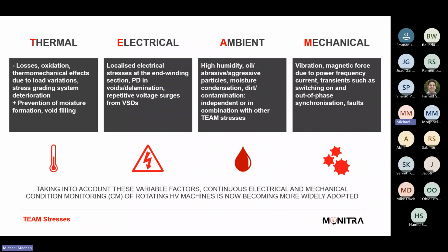So PD is a symptom and not a cause of a failure. Obviously when we look at PD, we're not looking at the potential cause. PD is purely a symptom of a potential failure mode. So an end winding discharge, a contaminated winding, a loose wedge or surface tracking voids. So the PD can help with identifying the root cause, which is why PD is such a useful tool for looking after machines and being able to ensure that you've got that machine in a healthy state throughout its life.